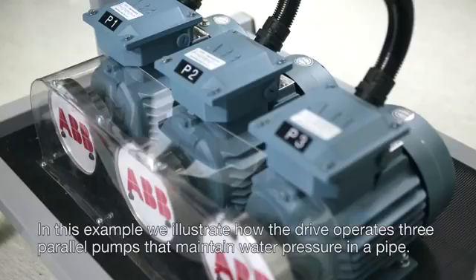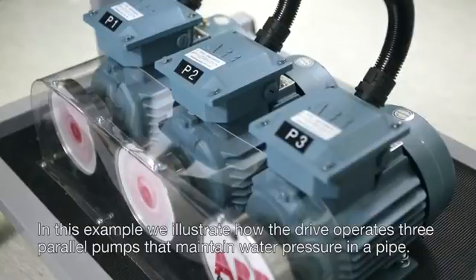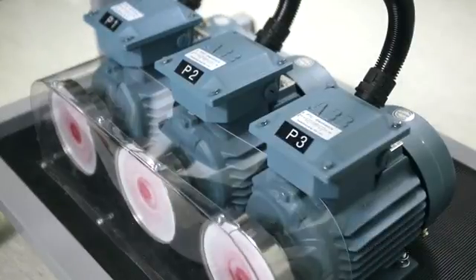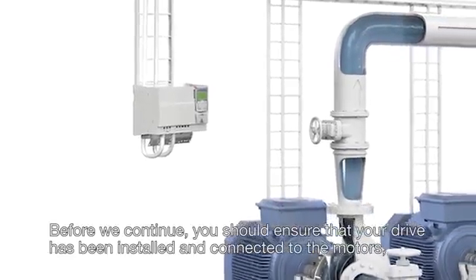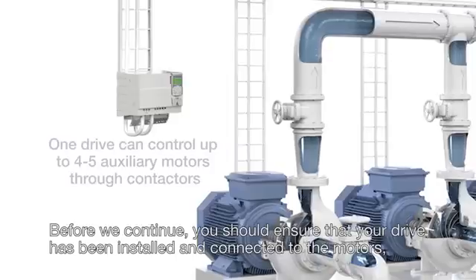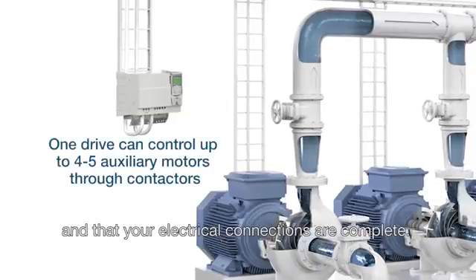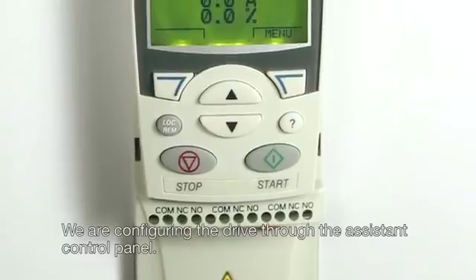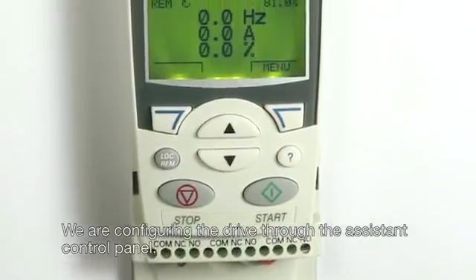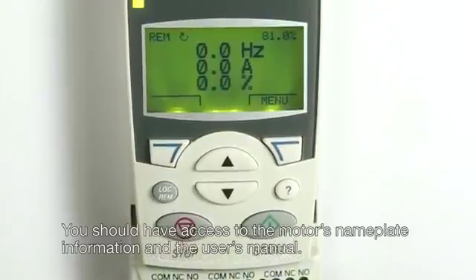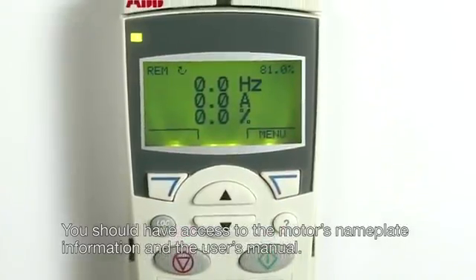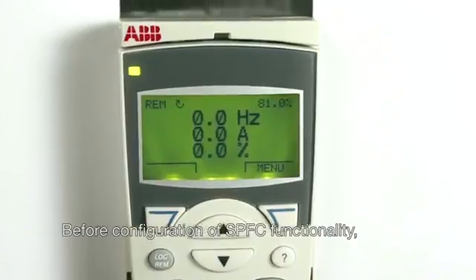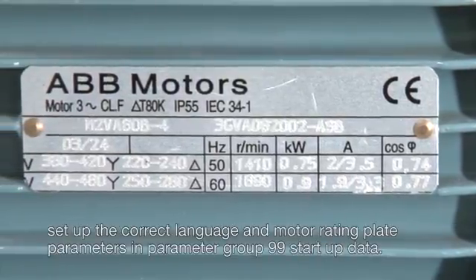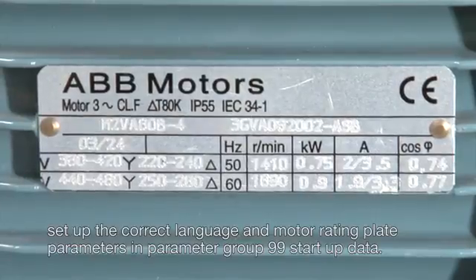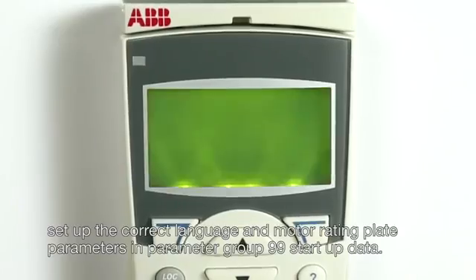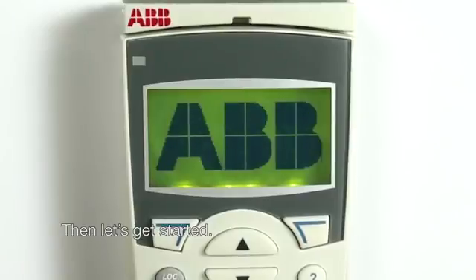In this example, we illustrate how the drive operates 3 parallel pumps that maintain water pressure in a pipe. Before we continue, you should ensure that your drive has been installed and connected to the motors, and that your electrical connections are complete. We are configuring the drive through the Assistant Control Panel. You should have access to the motor's nameplate information and the user's manual. Before configuration of SPFC functionality, set up the correct language and motor rating plate parameters in parameter group 99 Startup Data. Then let's get started.